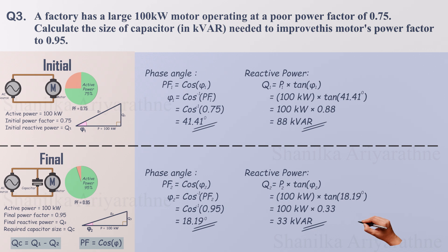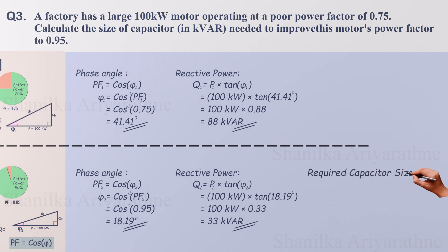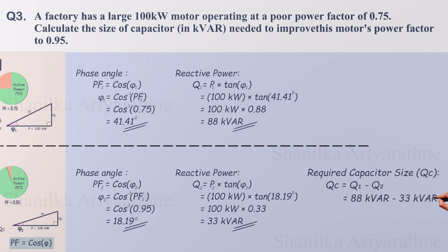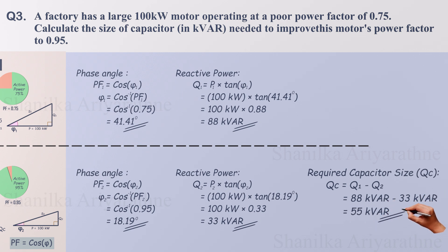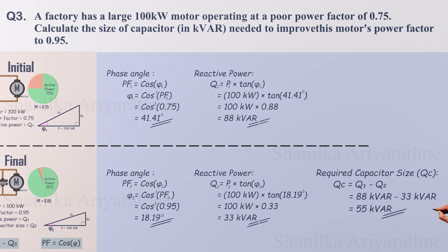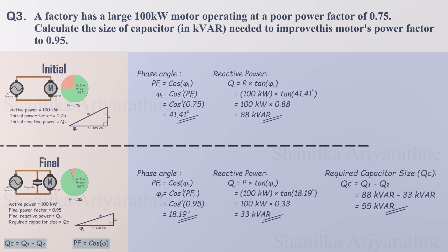Now the final step: we can calculate the capacitor size. Q1 is 88 kVAR and Q2 is 33 kVAR, so QC is 55 kVAR. We need a capacitor bank rated at 55.3 kVAR. This clever device will act like an electrical spring, storing and releasing energy in just the right way to bring our power factor up to that efficient 0.95.